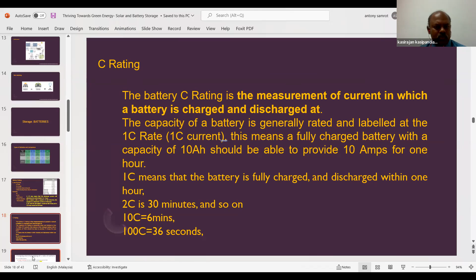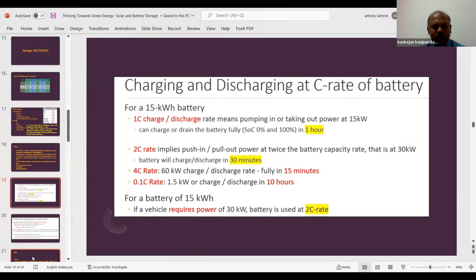For a 15 kilowatt hour battery, 1C charge or discharge rate means pumping in or taking out power at 15 kilowatts, charging or draining the battery fully in 1 hour, between 0% and 100%. 2C means within 30 minutes, and 4C within 15 minutes. These are some examples of C rate.